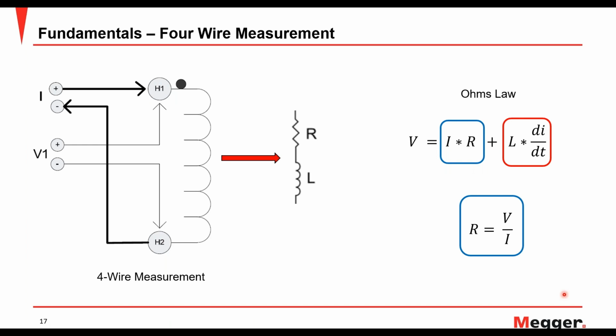What is the principle behind transformer winding resistance measurement? Firstly, we are using DC current in order to measure resistance on the transformer. Now, why do we use DC? Why not use AC? Because transformer is an AC equipment, right? Why does it make sense to use DC?